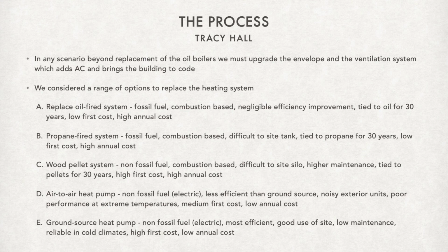Our last option, which is what we're ultimately proposing, is ground source heat pumps. A ground source heat pump does the same thing an air-to-air heat pump does, except it moves heat into the ground in summer. If you have excess heat in the building, you dump it into the ground through a system of wells, circulating water in a closed system. In summer you dump your heat into the ground; in winter you draw that heat back out of the ground to dump into the building.